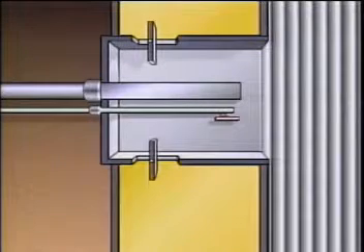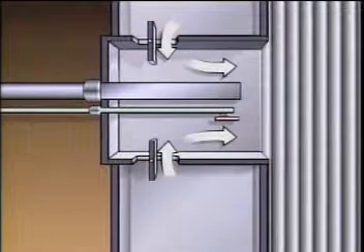A boiler generally has many burners located around the boiler furnace to provide an even source of heat to convert water into steam. Typically, burners are located in a wind box, which evens out the flow of air so that each burner is supplied with approximately the same amount of air.